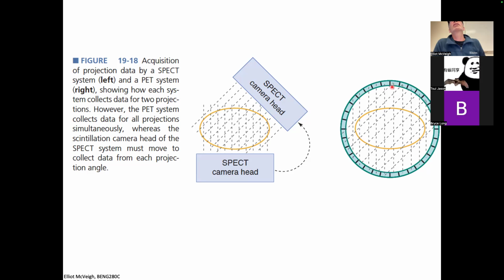That's the thing that usually, or used to, take a long time because, as we'll see, you use iterative techniques. You take a guess and you say, if my image was this perfect image that I have here, what would my raw data look like? You forward project your image estimate and look at the differences between that and the actual raw data I have. And then you correct those differences and make a new guess at the image. And you just iterate on that loop. And that takes a while. That takes like half an hour or something, or used to.